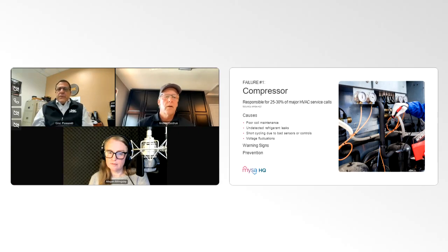So this is where facility managers are faced with figuring out what the HVAC system is doing or why it's not working. HVAC components themselves are very highly integrated, so multiple issues may be occurring. Sometimes what appears to be one issue may be a symptom of another failure. The compressor itself absolutely is the heart of an HVAC system, whether AC or heat pump. They can fail in many different ways. A warning sign typically is the space not meeting set point temperatures, or you could be dealing with insufficient heating or cooling, even though the HVAC system itself is running.